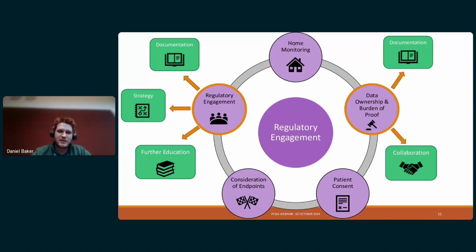And I think there was some discussion around assays and assay context of use. It seemed that if an assay that had been developed and validated was being used within its context of use or intended purpose, then there'd be no additional assessment needed. It could be used off the shelf style. However, if an assay or device was being used outside this context of use, whether that might be a different therapy area or a different patient population, or venous versus capillary, then there may be some additional validation required.